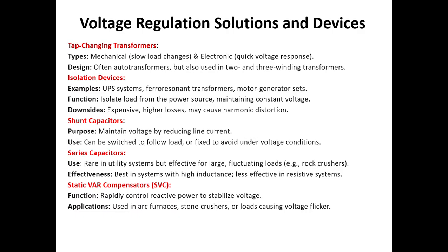So that's why you may get some harmonic distortion in the power system. Again, that is part of power quality, where you get harmonics. That means power quality issues such as harmonic distortion. The next point we are going to discuss is shunt capacitors. We can use the shunt capacitor to maintain the voltage constant. Can we switch to follow the load, or fix it, to avoid under-voltage conditions? This is one way we use the shunt capacitor to maintain the voltage constant.